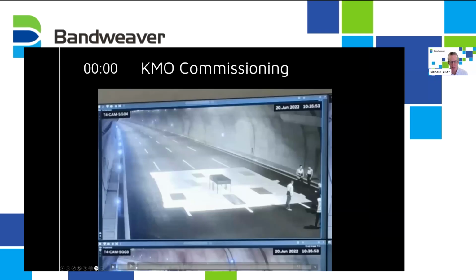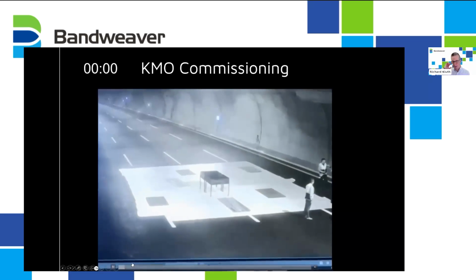It was recorded using a mobile phone in the control room, but what you'll see is the timer starts, they light the pan at 6 seconds, and it's detected within the SCADA system at 36 seconds. I won't talk over it. I'll let you see, and you can see an example of how quickly it detects at the commissioning test level.